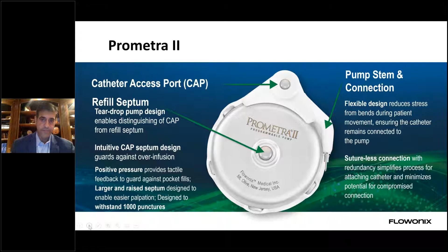Also, this refill port is designed to withstand up to 1,000 punctures. The pump stem and catheter connection site is also very flexible, reducing any stress at this connection. And there's a sutureless connection, which simplifies the process for attaching the catheter, which goes right on that stem, and minimizes any potential for a compromised connection.